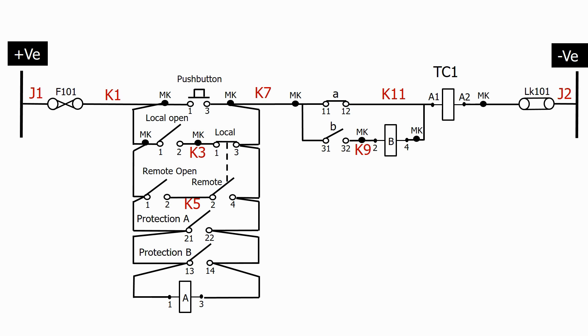As we can see, the K1 signal is looped across several parallel contacts, but as they are connected to the same signal, all of the wires are labeled K1. Although some utilities will put an additional letter or number on the end so that you know which wire in the loop you're looking at. So we might get K1A, K1B, K1C, K1D.